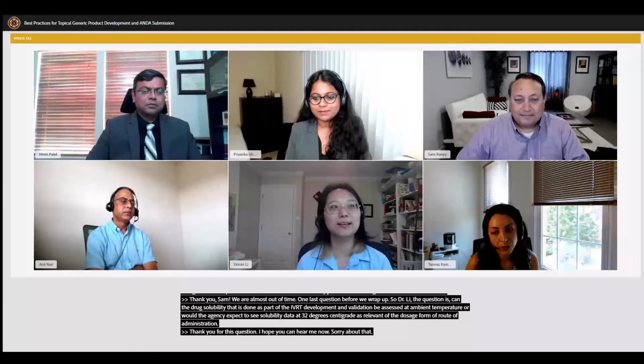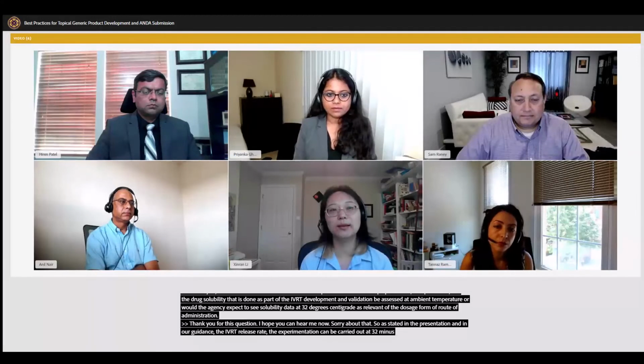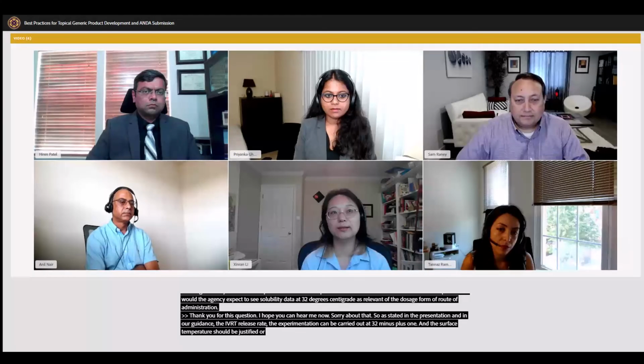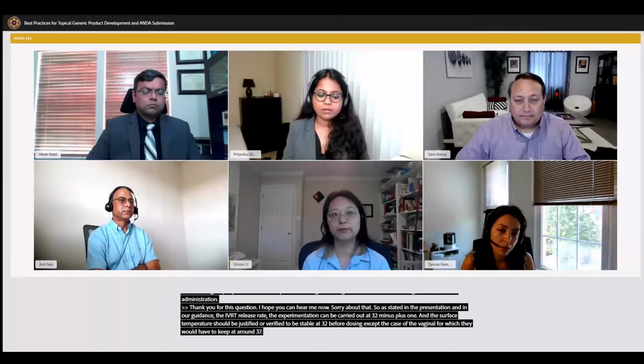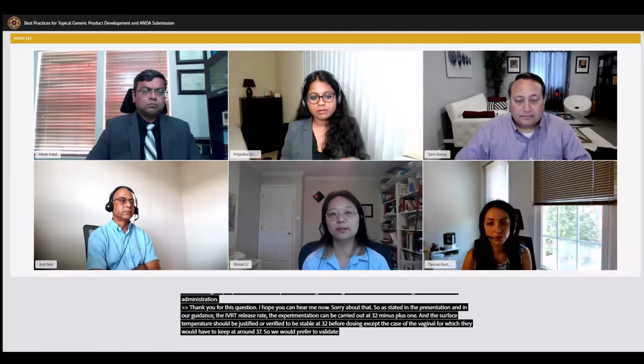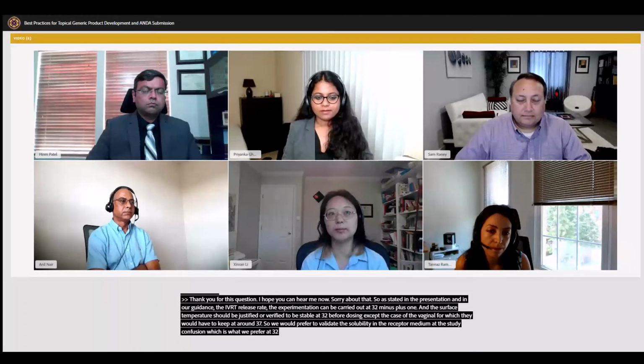So as stated in the presentation and also in our guidance, the IVRT release rate experiment should be carried out at 32 ± 1, and the membrane surface temperature should be justified or verified to be stable at 32 before dosing, except in the case of the vaginal drug product, for which the temperature should be kept at around 37. So we would prefer to evaluate the drug solubility in the receptor medium under the study condition, which is, we prefer, at 32 or 37, depending on the drug product.